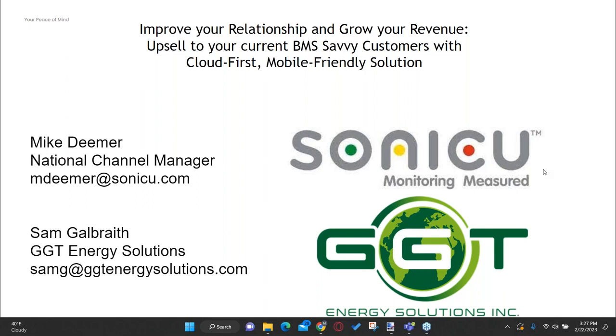And as part of that, we have what we call your calibration info page. You bring up that page, and it shows you every single sensor currently plugged in, what the calibration date was, what the expiration date is, as well as a notification if you have something one month or less before the calibration expires.